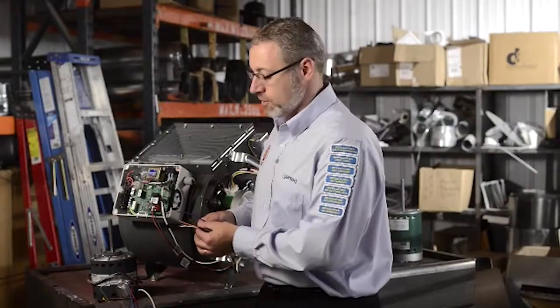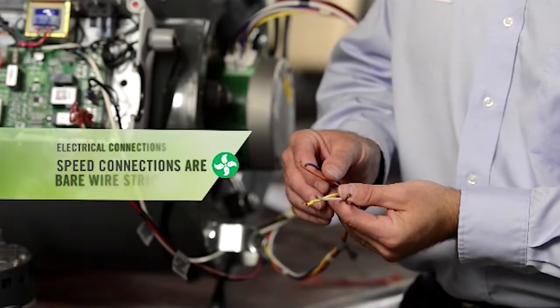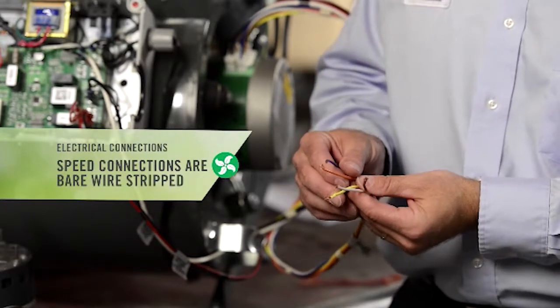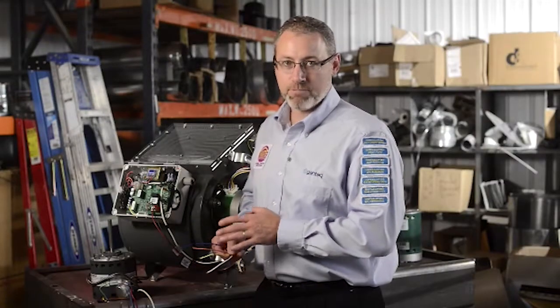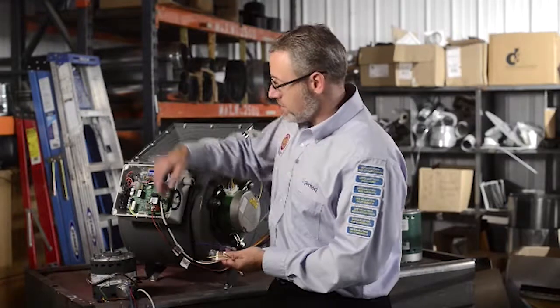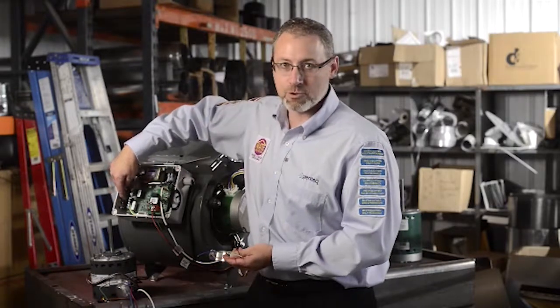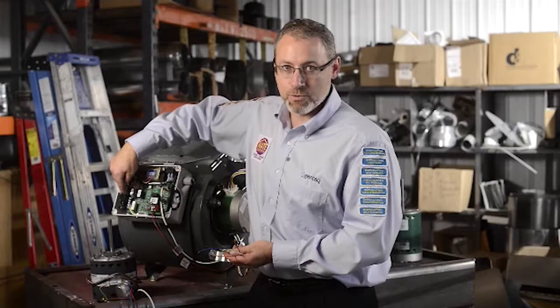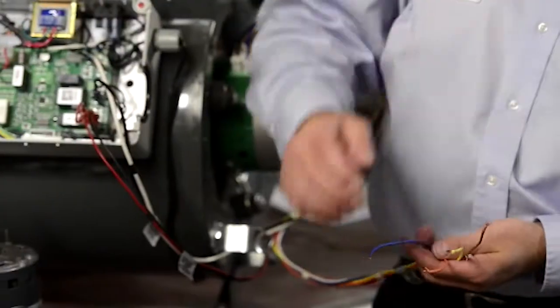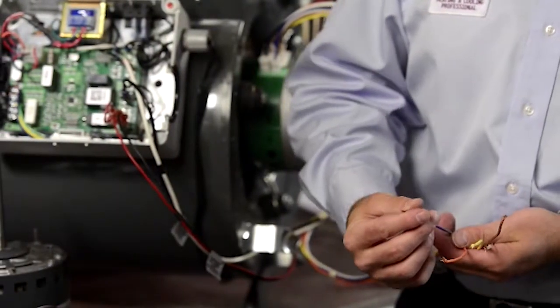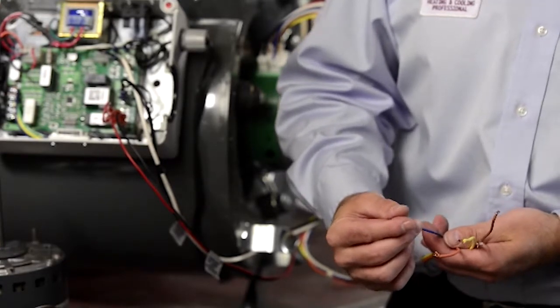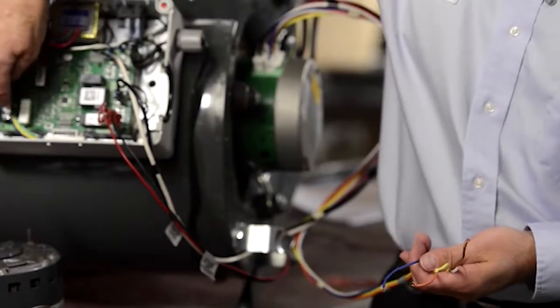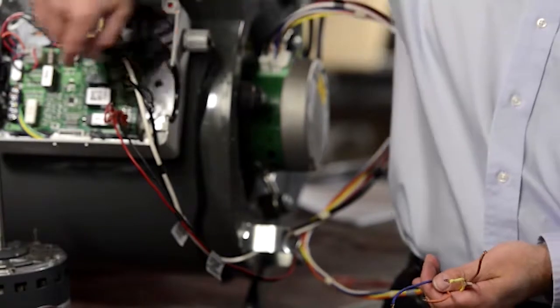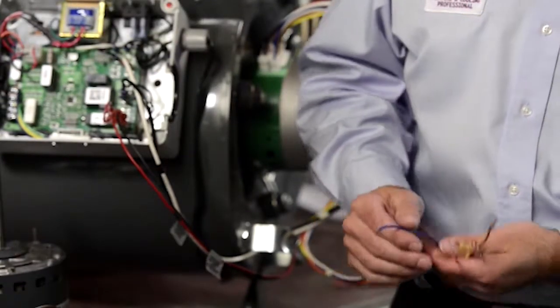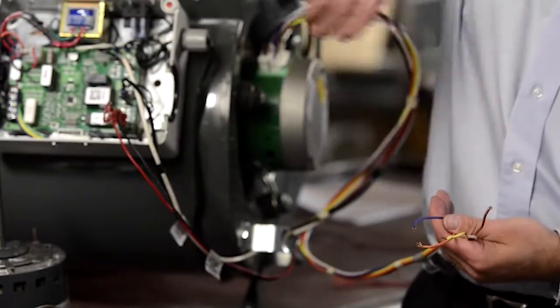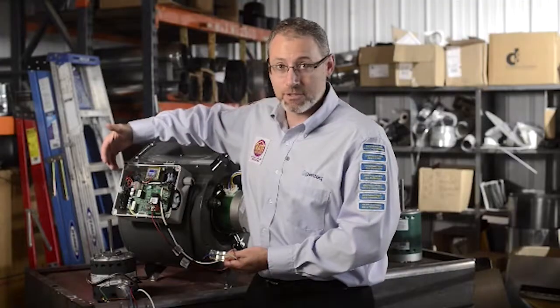Something I didn't talk about earlier, if you notice, our speed connections are bare wire stripped. The reason why we left these wires bare wire stripped is because if you look at the thermostat connections on most control boards, they're little screws and they're very close together. So we wanted to put either a fork terminal or an eyelet terminal on these wires, but we found that in most cases you're probably going to end up cutting it off because it's not going to fit under those terminals.